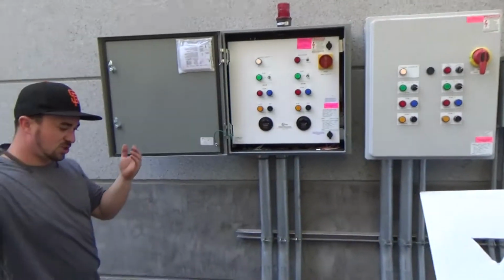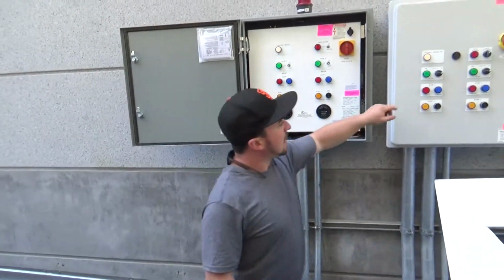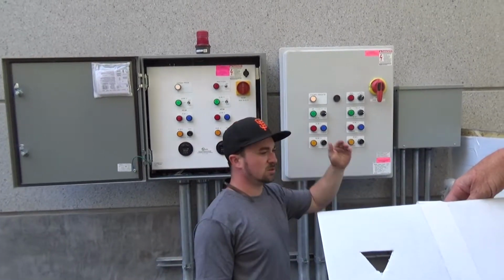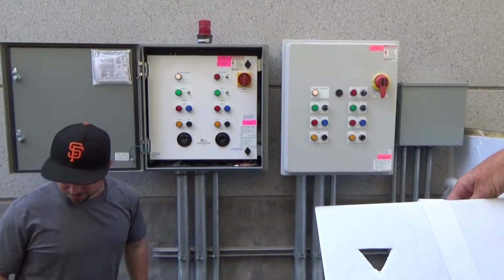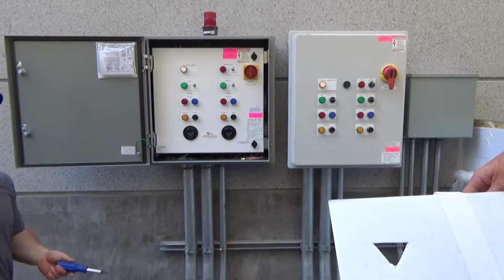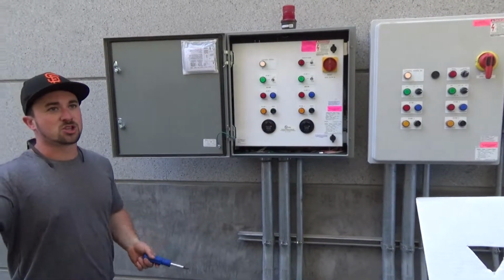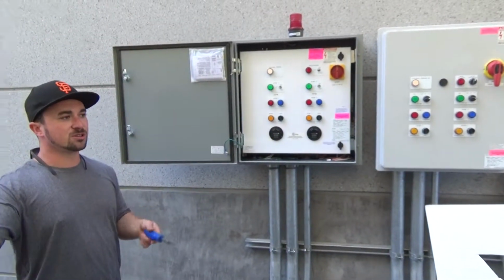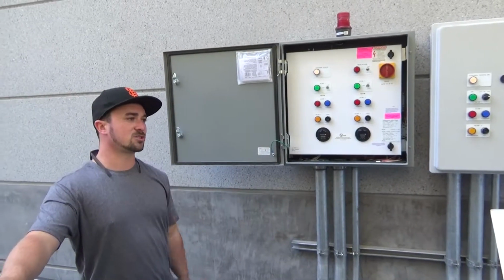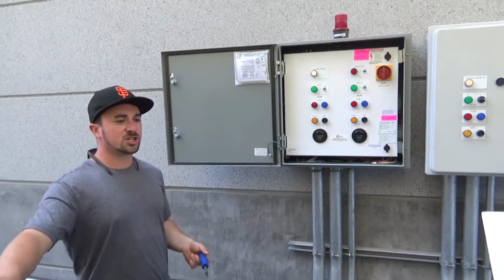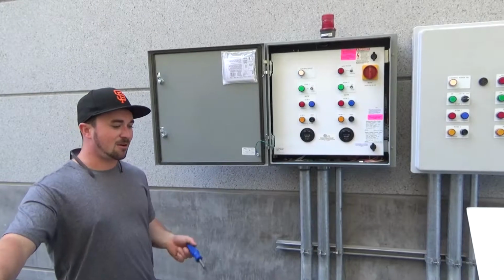And the purpose is, say you sit here and you just hold this thing in test mode and you let it just drain down as far as it'll go. And it gets air in that volute. The pumps can't pump air. So these guys, I already know, I was here during the startup of this one and I just did the startup of that one today. They've drilled holes in the discharge piping so that you can get that air out.